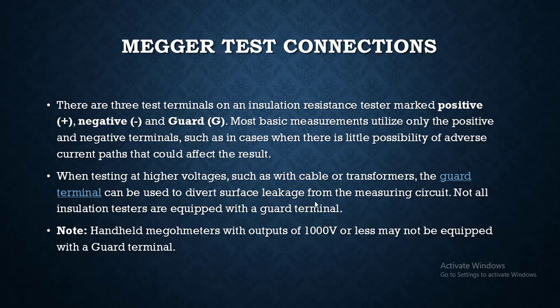When testing at higher voltages, such as with cable or transformer testing, the guard terminal can be used to divert surface leakage from the measuring circuit. Not all insulation testers are equipped with the guard terminal. Handheld megohmmeters with an output of 1kV or less may not be equipped with the guard terminal.